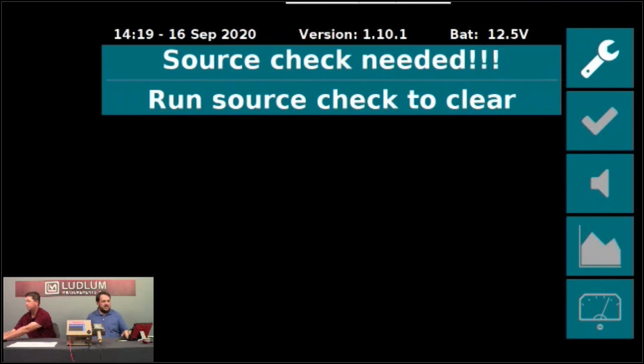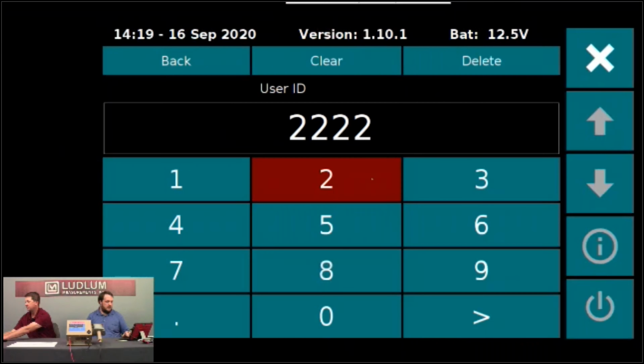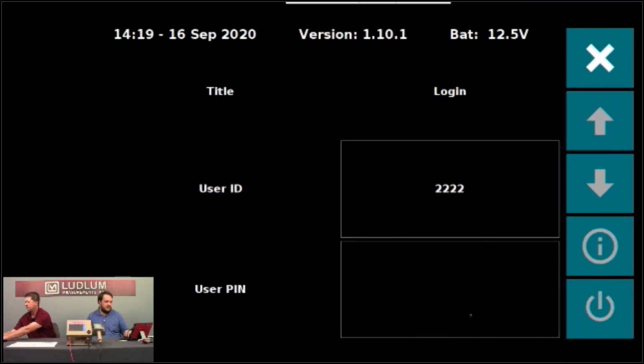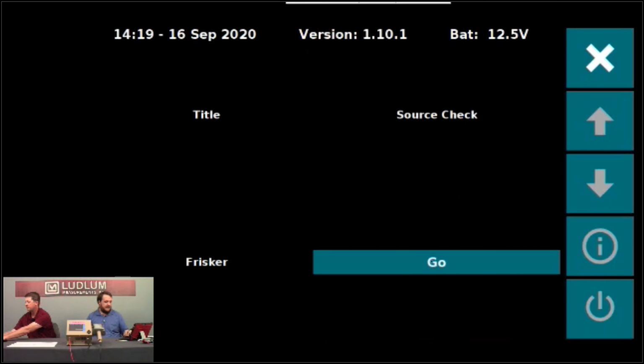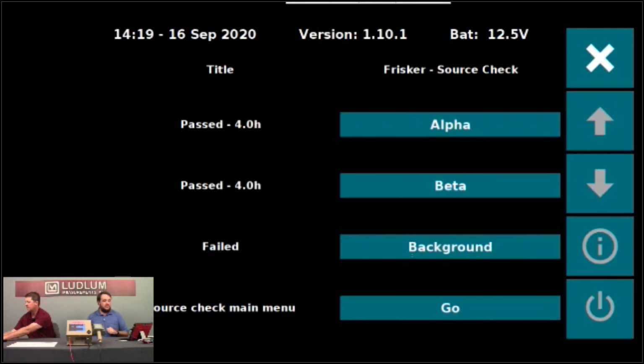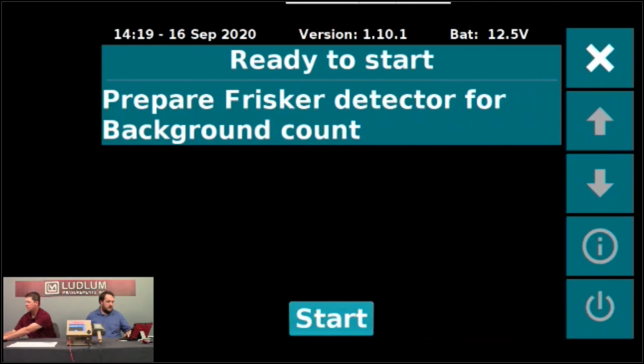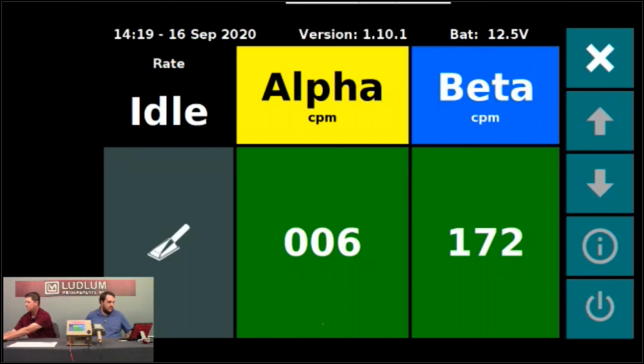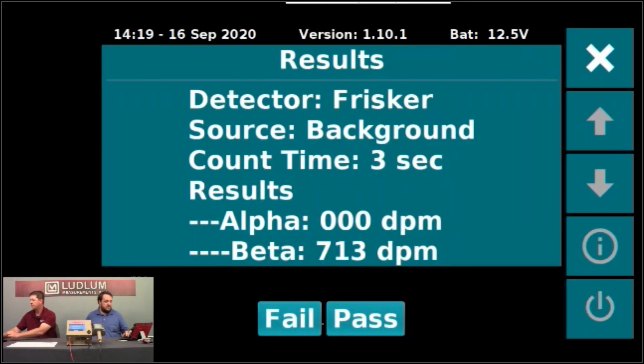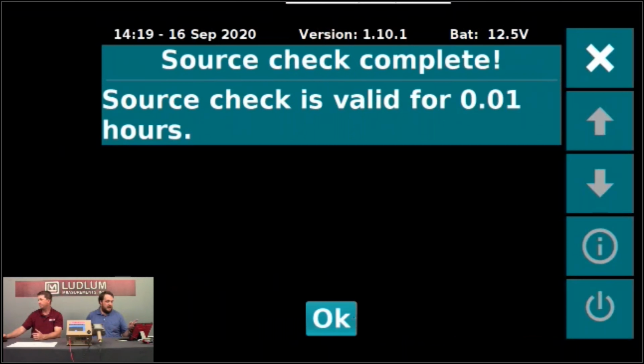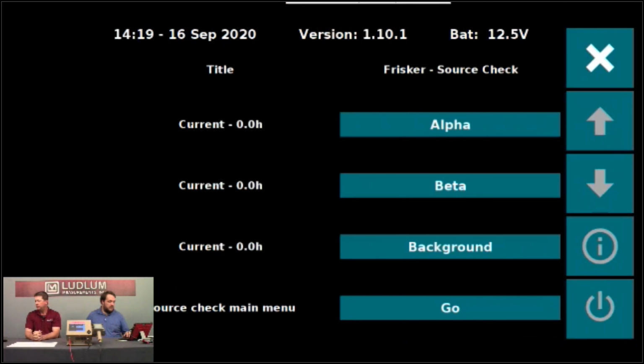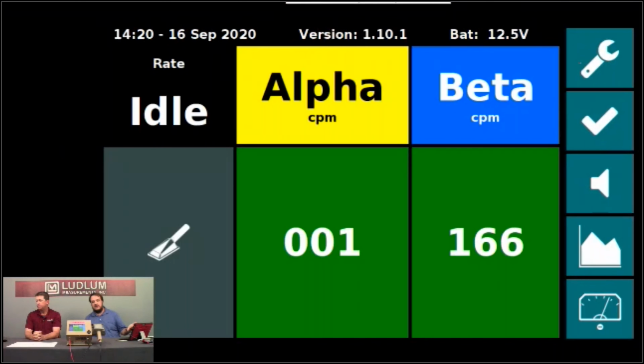If that's the case, you can still go back into the settings menu. Oop, too many. And select the Frisker again. And we'll do the background again. Start it. It'll run through the count, give us the results, and this time I'm going to hit pass, and it tells us how long that it's valid for. And over here, all of these now say current. So that means that the source check is basically in a valid state. If we go back to the readings menu, the unit is usable again.